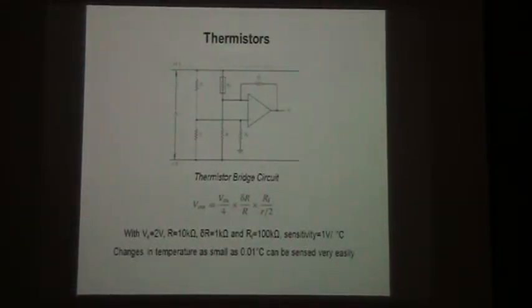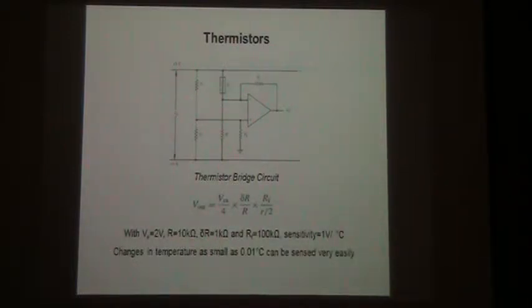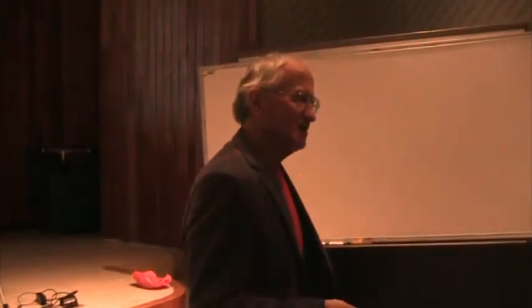What does it mean? The threshold, look, can be very small, 0.01 degrees centigrade, because we have a huge sensitivity. We cannot get such a threshold with a platinum-based resistive temperature sensor. Yeah? So looking at the sensor, we can immediately conclude what sort of parameters, both static and dynamic, we can expect. Now, what can we expect from the repeatability point of view?